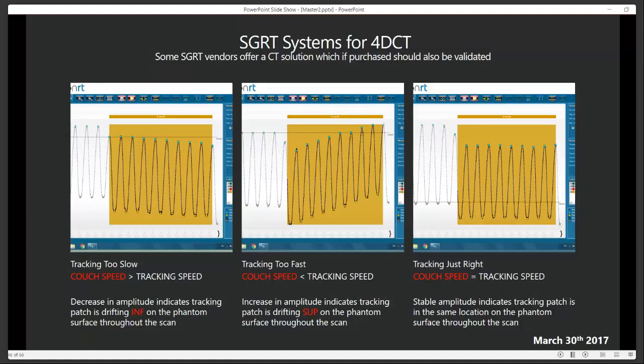The reason this is important is you don't want your tracking to fall onto an immobilization device, onto a body mask, onto a vac-lok bag, or onto a region of the patient that just isn't moving with breathing, so that you lose the signal in the middle of your 4D CT, which then ruins your 4D CT. The majority of people who tell me that they don't like their SGRT system for CT, for 4D CT, have never done this test, and usually what I'm seeing when I go to these centers is that the tracking patch ends up on an immobilization device because they have a gate or a paddle or something very close to where they're tracking the breathing motion.